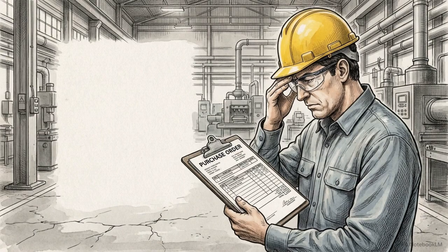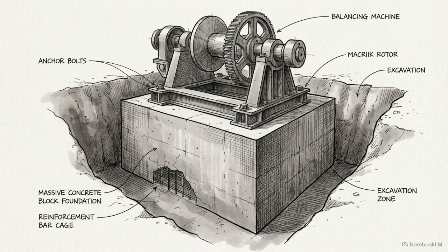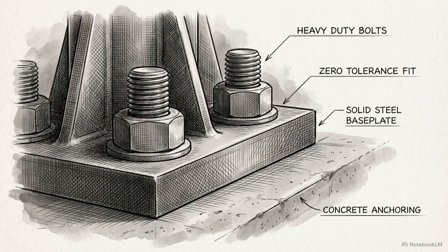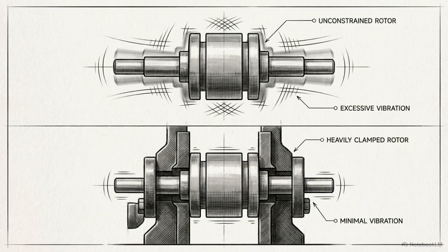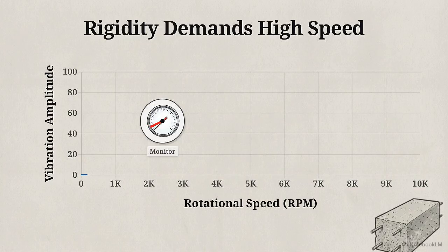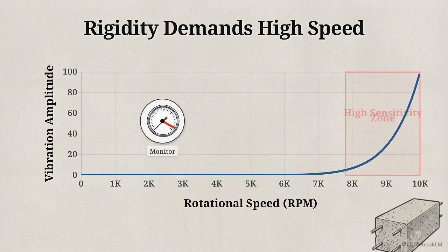their production line. The hard-bearing machine's defining trait is pure rigidity, which requires anchoring the equipment to a specialized, permanent concrete foundation. By locking everything down, the structural base actively fights the spinning rotor, restricting the physical amplitude of any unbalance or vibration. Looking at this chart tracking vibration amplitude against rotational speed, we can see the result of that rigidity. Because the machine suppresses the shaking, it has to spin the rotor at high speeds to generate enough force for the sensors to detect it.